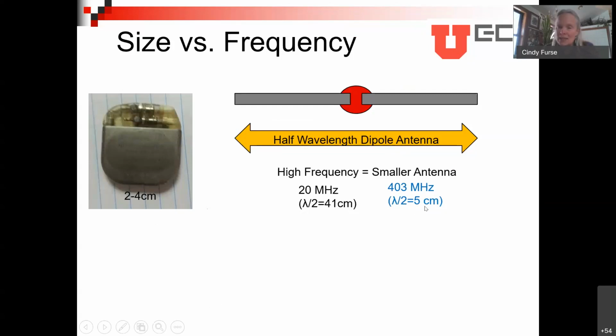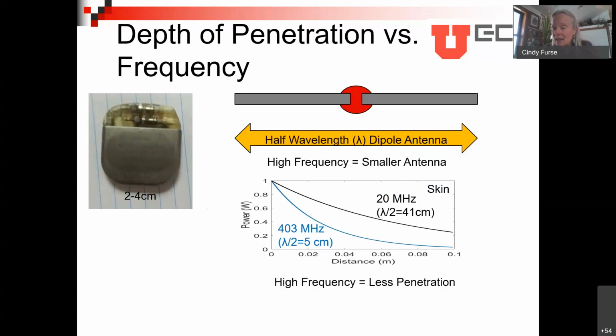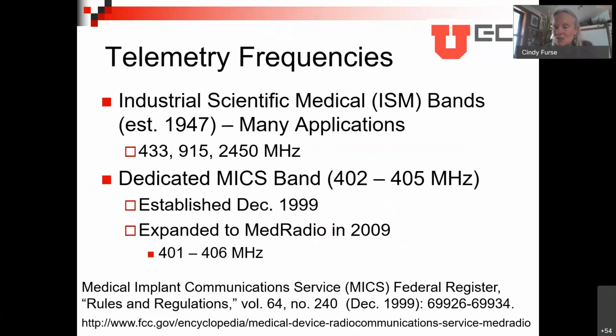almost fit, not quite. And again, the challenge is if we went to lower frequencies, it's better for going deeper into the body. We don't have as much attenuation. But if we go to higher frequencies, we can make the antenna smaller, which is what we want. So we certainly have this trade-off, this push and pull between the frequencies. And the frequency that was chosen was 402 to 405 megahertz. So these are the frequencies that can be used for telemetry or data and power communication.